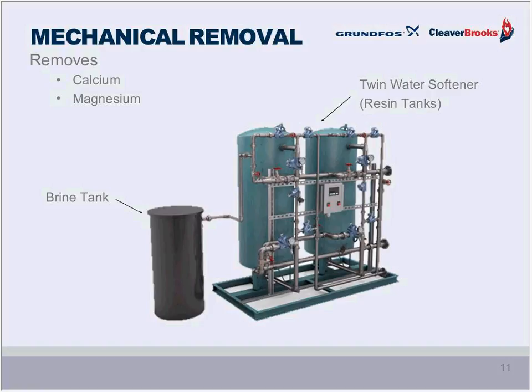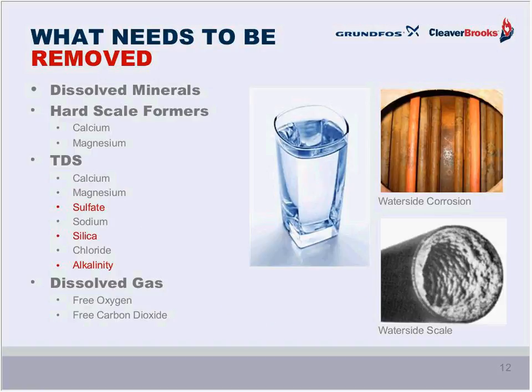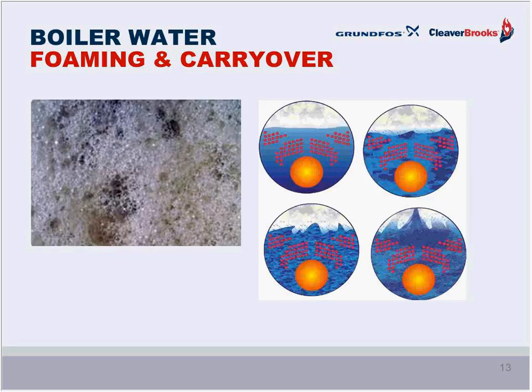And if a twin softener is used, as is shown here in the picture, the removal of these nasties can be continuous as one tank regenerates while the other tank is in service, and of course they rotate back and forth. And continue with mechanical removal of impurities. We see things like sulfate, silica, and alkalinity, which cause all sorts of problems in the boiler, including unstable water line, which we normally refer to as shrink and swell of that water line, in addition to foaming of the boiler water, owing to random boiler outages due to unexpected low water cutoff conditions, and then steam carryover, which ultimately leads to process upsets and possible and dangerous water hammer.